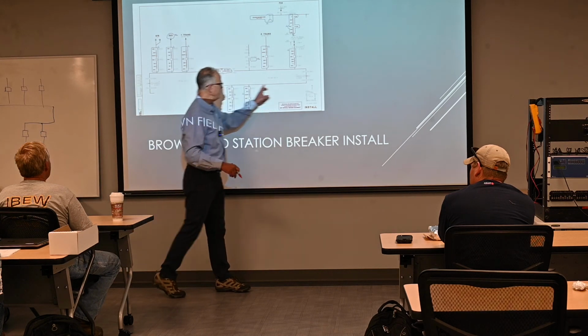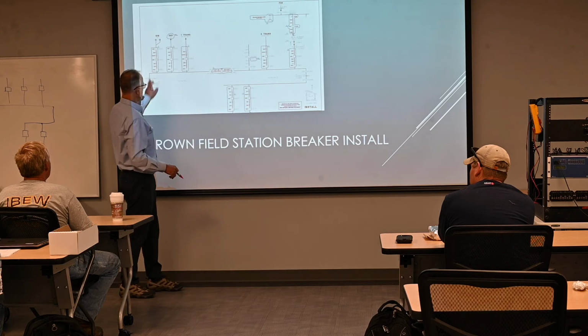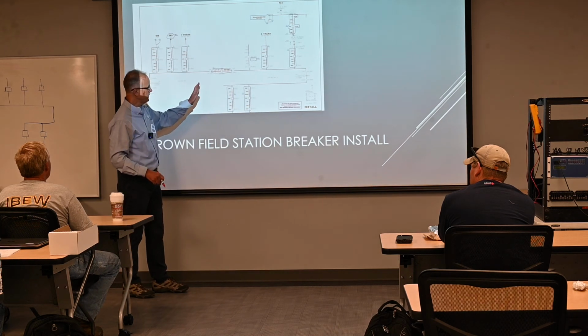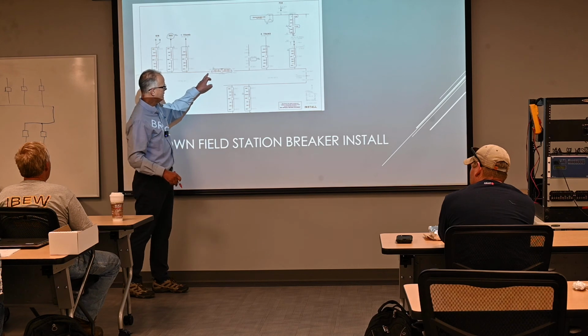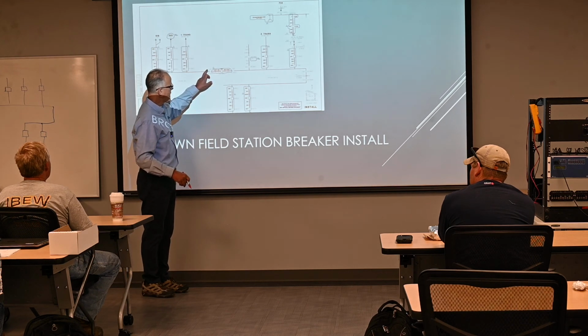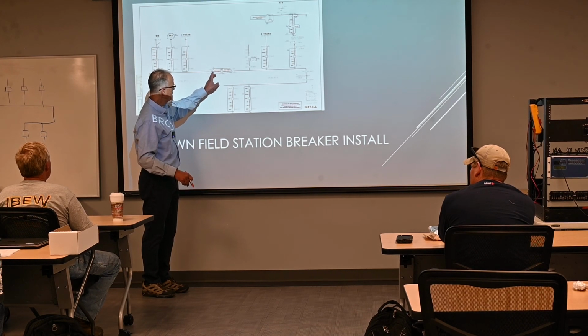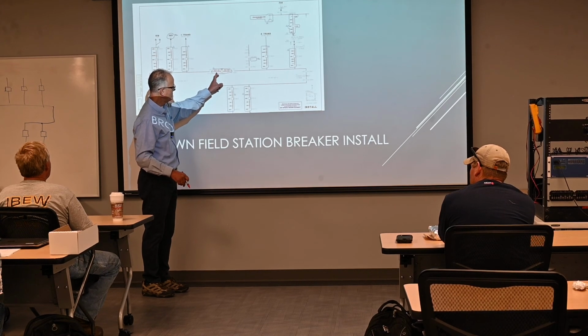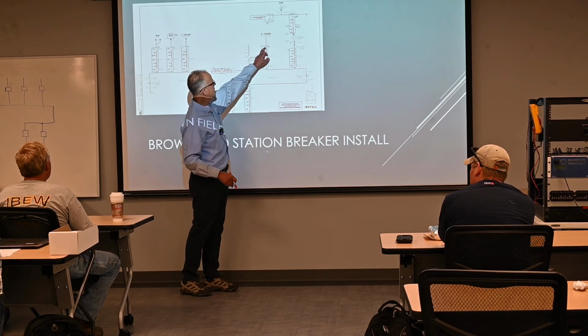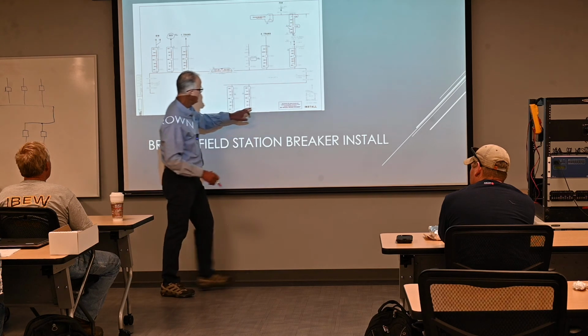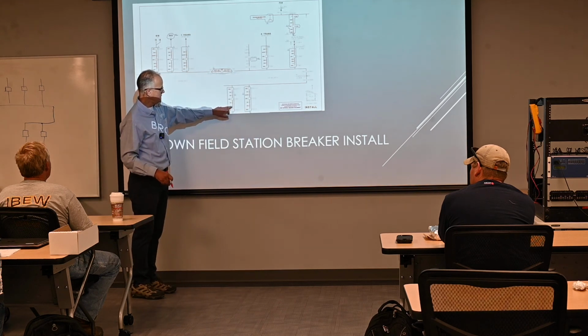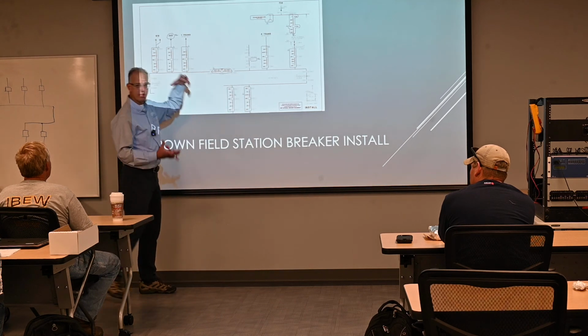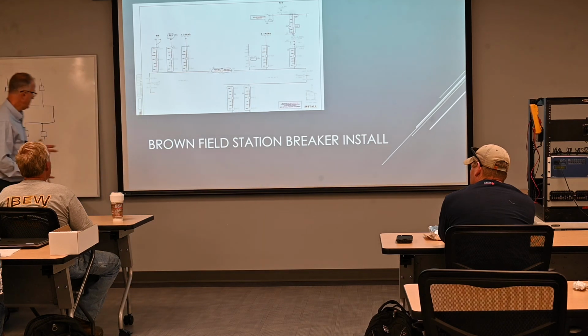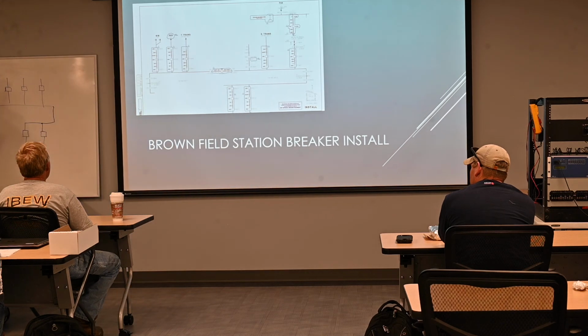And there's a bus section 1. So there's two different bus differential protections. One that, and I'm going to draw it in over here, but it wraps, it protects from this CT here all the way through to this CT, this CT, this CT, and this CT. So anything within that zone of protection, it's called, is protected by the bus differential protection.